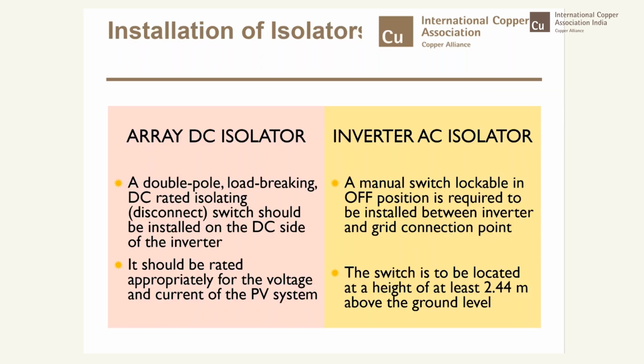In the earlier picture, we saw array isolation as a DC isolator, which has to be a load breaking category, and an on-load isolator also to be provided on the AC side. But here there is another insistence, to be operated by the utility people, which has to be under control and which can be secured only in off position. You can use the padlock only when the isolator is in off position, and the contacts have to be visible from outside the box through an acrylic or transparent outer cover.